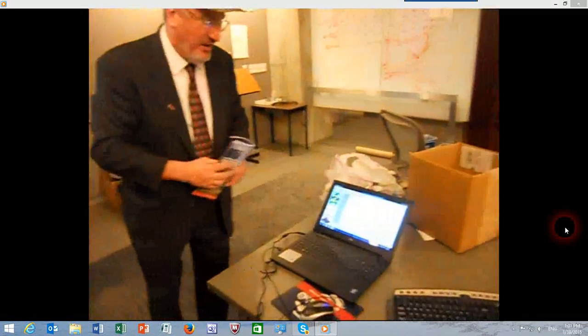The power, efficiency, vibrations, FFT spectral analysis of vibrations, I can see the first frequency at 55 hertz, the second and third. I can also look at tabular data and download it to an Excel spreadsheet and analyze the data. You do it online, live, taking data every 2 seconds.